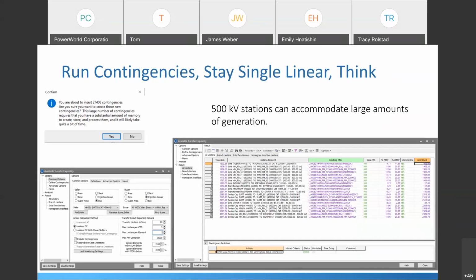And then based on maps and one's knowledge of the system, you can look at it and say, all right, that Hatwai Lower Granite limiting contingency comes back with a problem at 230. That's a keeper. And then you've got this Malin Round Mountain problem. That's not really a Hatwai kind of thing, right? Even though the PTDF and the OTDF are bringing big numbers back, it's because there's a lot of generation in California, and your WEX sync is going to show that. So those could be something that you would consider just skipping.